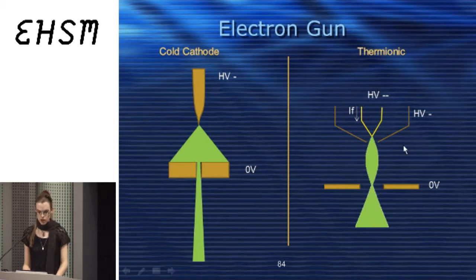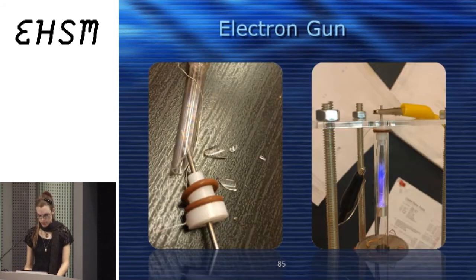The best thing about the thermionic is you can see that the entire electron beam is conserved and ends up going down the beam line, whereas with the cold cathode one you lose most of your electron beam because you're basically just putting a mask in front of it, but it does work, and it works in low vacuum conditions, which means it's hackable. And here's one that, yeah, it broke, but it shows you the internal structure.